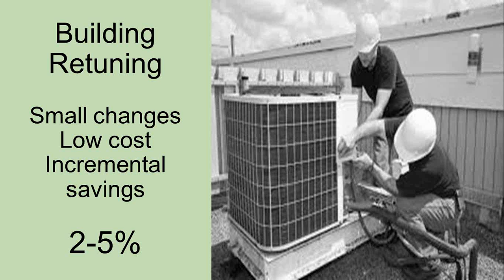Building retuning provides a way to have an immediate impact, especially in the often overlooked small building market, which includes many multifamily buildings. Small buildings are considered those under 100,000 square feet that frequently don't have any centralized building automation system. These buildings often have package units for heating and cooling, controlled by zone thermostats.